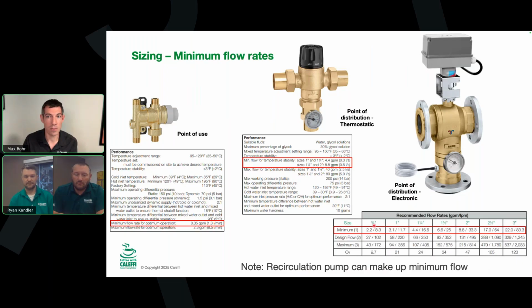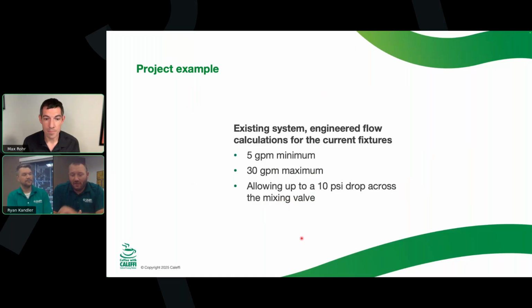If you have 0 GPM of flow, you can't move water over a sensor to know what to react to. So you can't get a radar reading of a car that's parked. There's no input there. Nothing has changed between those bounces of the radar. Kind of the same thing with either the sensor that's a wet well, that's an electronic thermistor, or the wax element inside of a thermostatic mixing valve. They need to react to something. You need to have some flow for that to work. Okay.